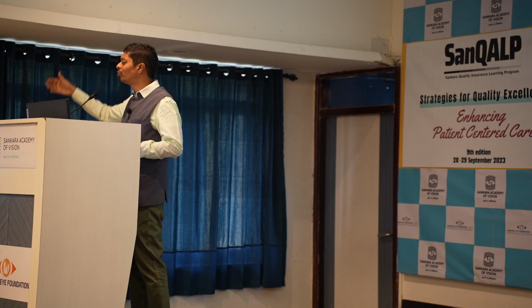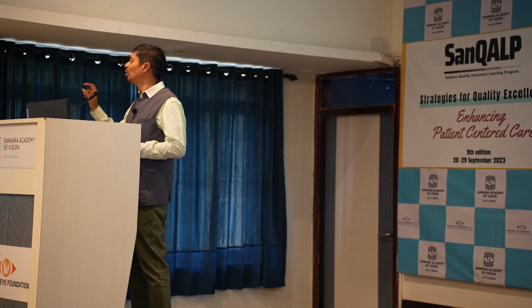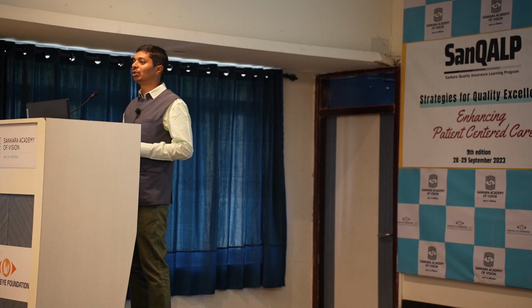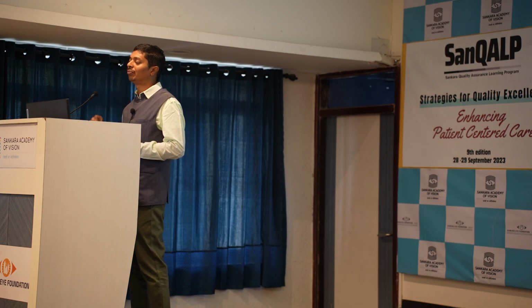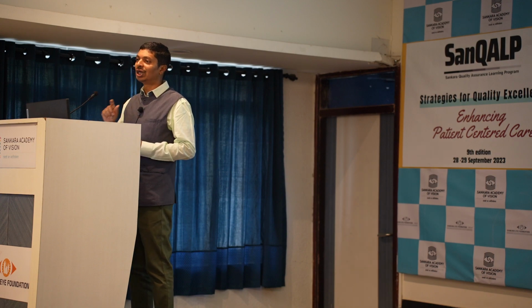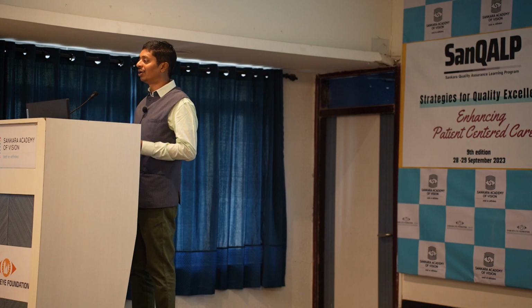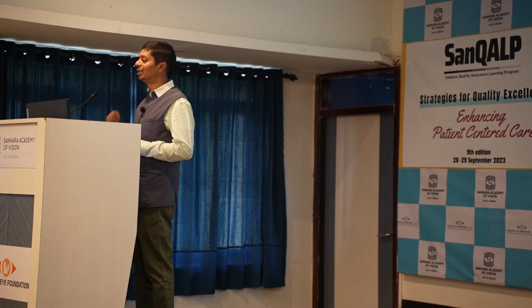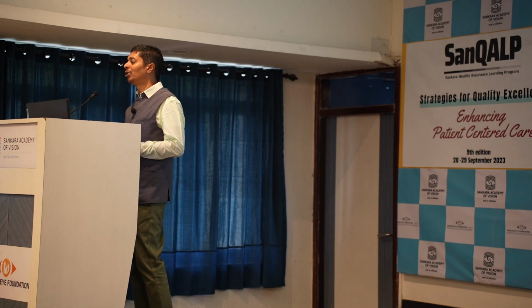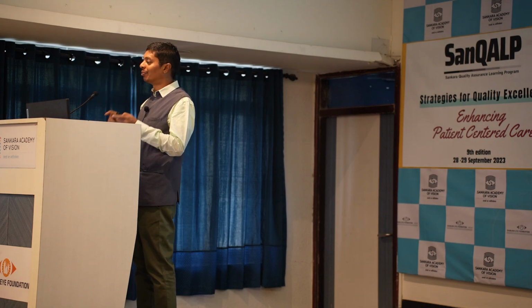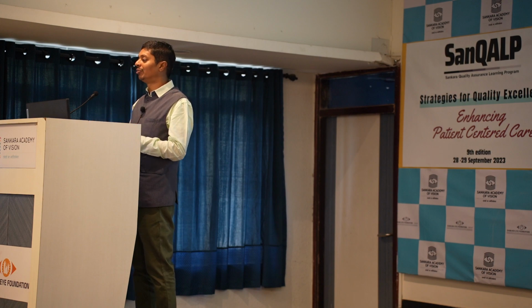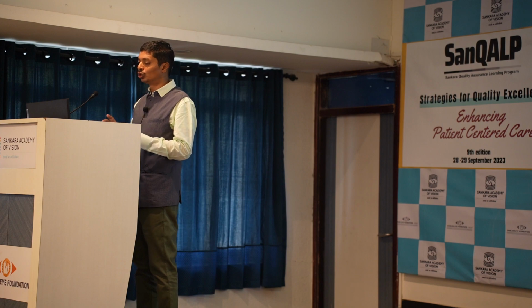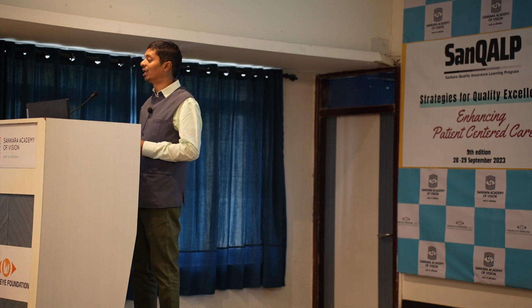Because, for example, if you go to the electrical panels, there are so many MCBs and switches. I am intending to switch off for an operation theatre, but we have put a tag for our ICU - is that possible? That is very much possible. If that happens, then my whole idea of putting a LOTO tag will be of no use, because when somebody is doing it, the power is actually still coming to the circuits going into the operation theatre. So those things can be checked as a final verification.